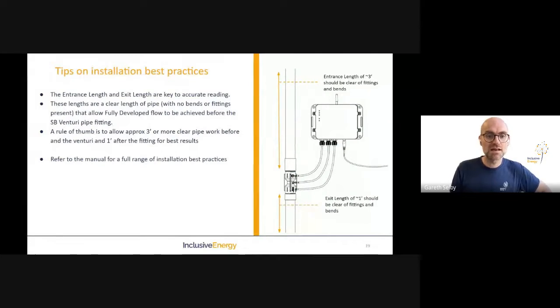If we go to the next slide. So I've added in this slide here just for customers maybe who already historically have bought our meter, because this is something that we found more recently to really help with accuracy. And it's the concept of the entrance length and the exit length, where you have a pipe length before and after our Venturi meter. And what we're trying to do is create an undisturbed entrance and exit length where you don't have any valves, tees or bends or any other fittings that might affect the flow. And that allows a fully developed flow to be achieved by the time it hits the Venturi or the pitot. And then we get the highest accuracy.